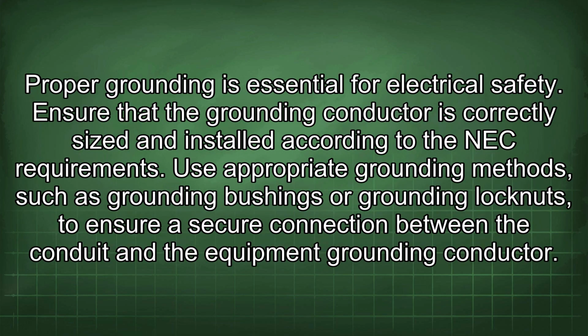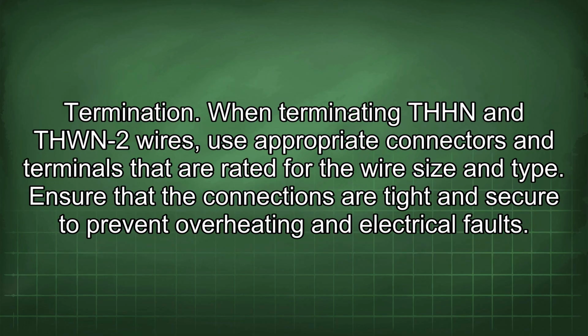Grounding. Proper grounding is essential for electrical safety. Ensure that the grounding conductor is correctly sized and installed according to the NEC requirements. Use appropriate grounding methods such as grounding bushings or grounding lock nuts to ensure a secure connection between the conduit and the equipment grounding conductor. Termination. When terminating THHN and THWN-2 wires, use appropriate connectors and terminals that are rated for the wire size and type. Ensure that the connections are tight and secure to prevent overheating and electrical faults.